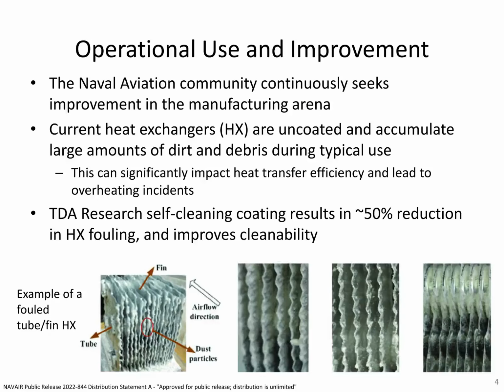Operational use and improvement. The naval aviation community strives for continuous improvement in the manufacturing arena. Current aluminum body heat exchangers are uncoated and accumulate large amounts of dirt and debris during typical use, as seen here. This type of fouling can significantly reduce the heat transfer efficiency and lead to overheating incidents of critical components.